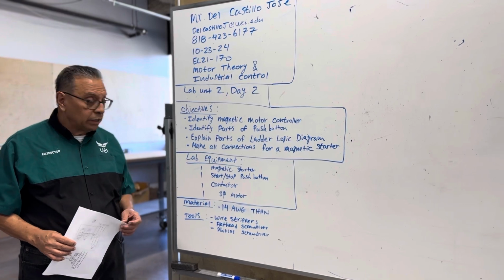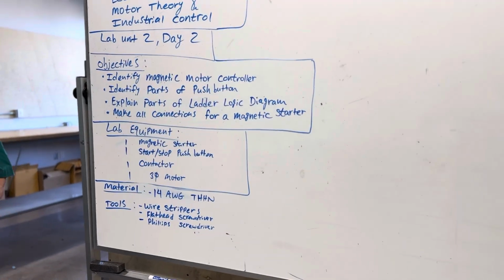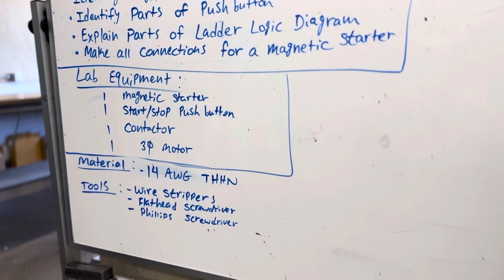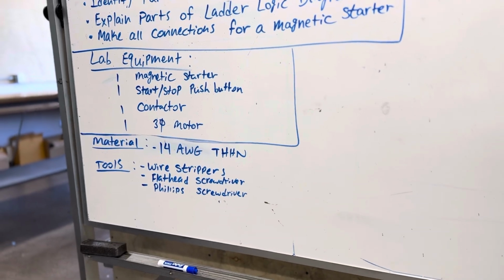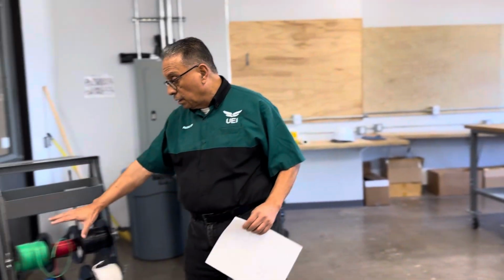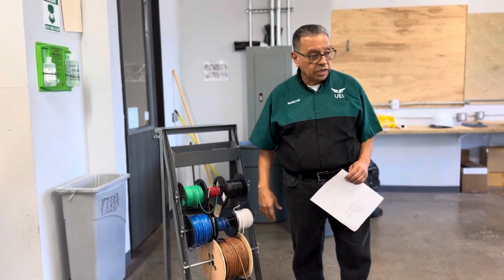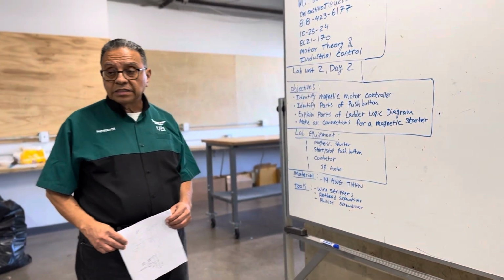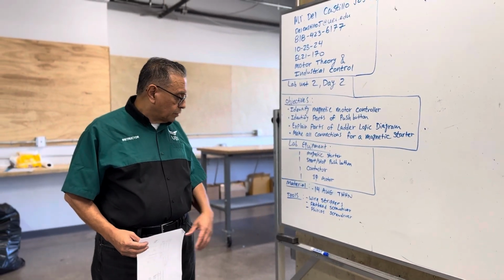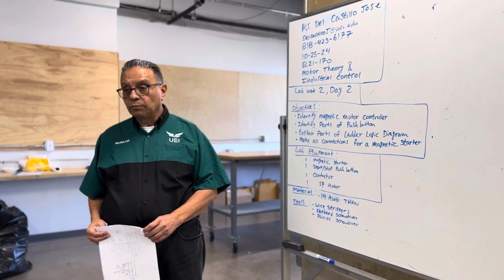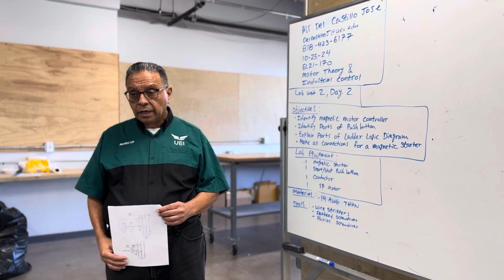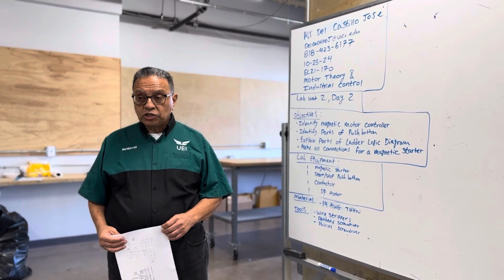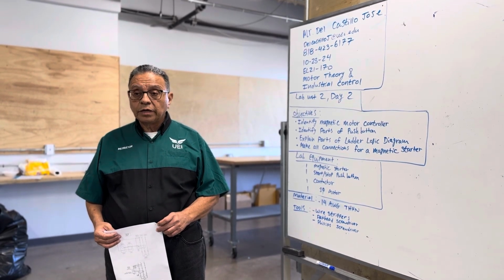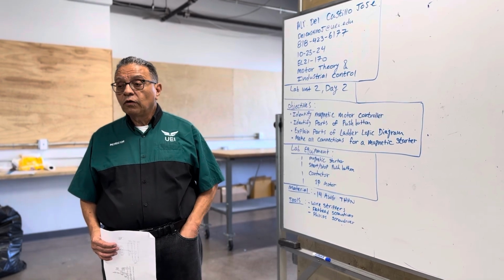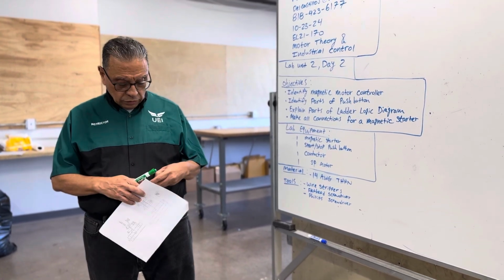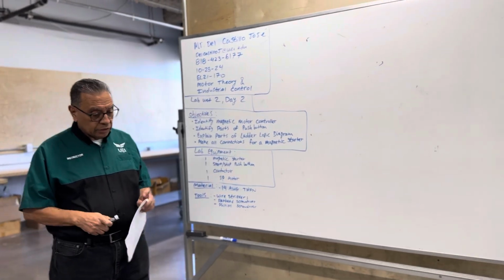Of course, the equipment that we need: a magnetic starter, a stop push button, and a contactor. We are going to use a NEMA 0 contactor and a three-phase electrical motor. We also need the wire, 14 gauge THHN, a wire stripper, flathead screwdriver, Phillips screwdriver, and the ammeter and multimeter to check the electrical current. Additionally, I will be using the NEC, Table 430.250, to check the full load current for the motor we are going to use, which is important to teach to the students.